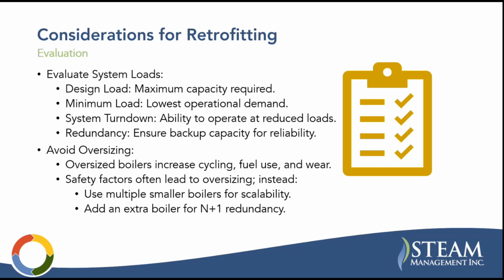So oversized boilers increase boiler cycling, fuel use, and wear and tear on mechanical components. And when I talk about cycling, that's basically the boiler not being able to continuously fire at the minimum load that the system requires. So it will have to turn on and off. Every time it turns on and off, there's a purge cycle.